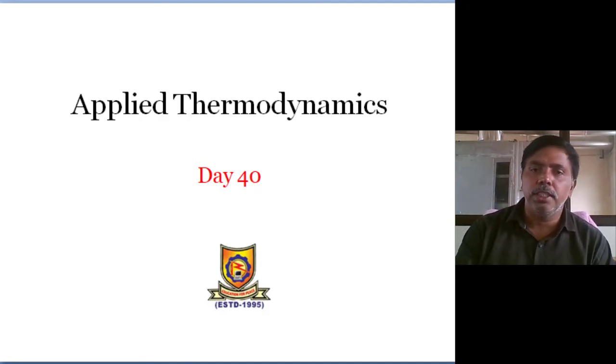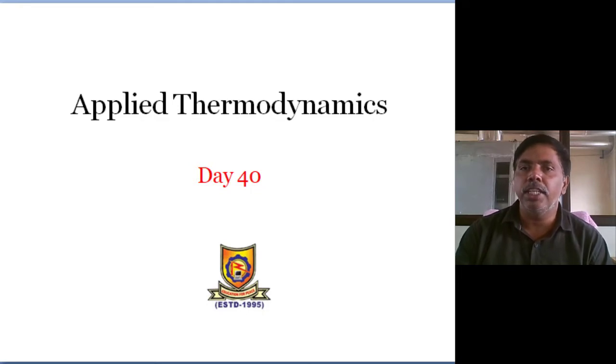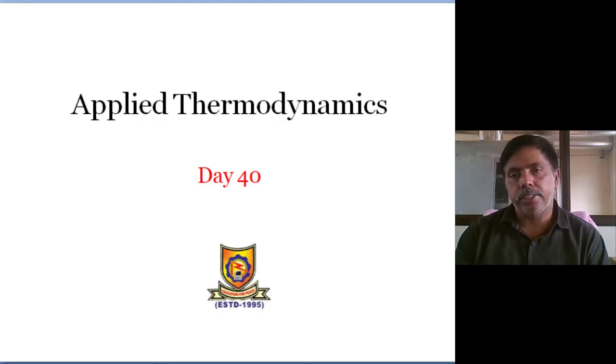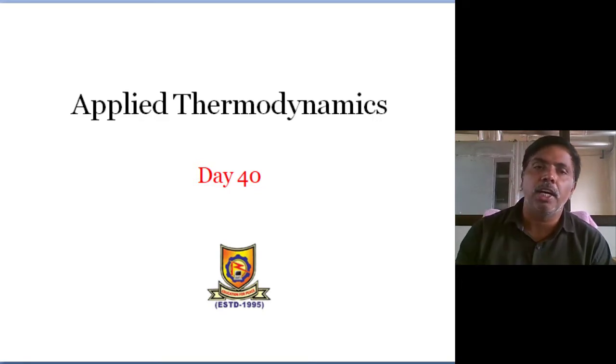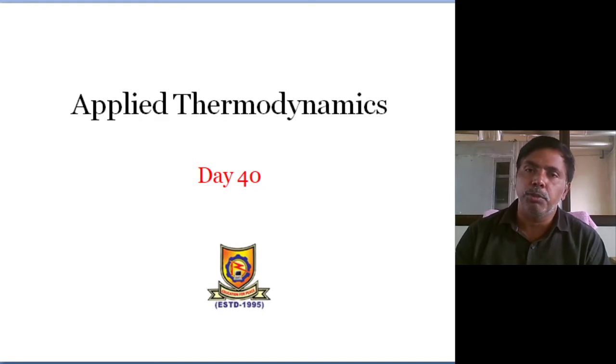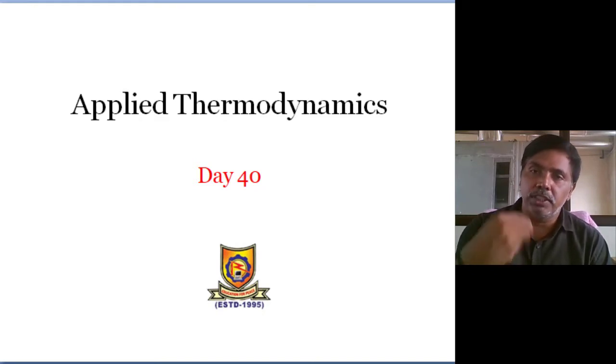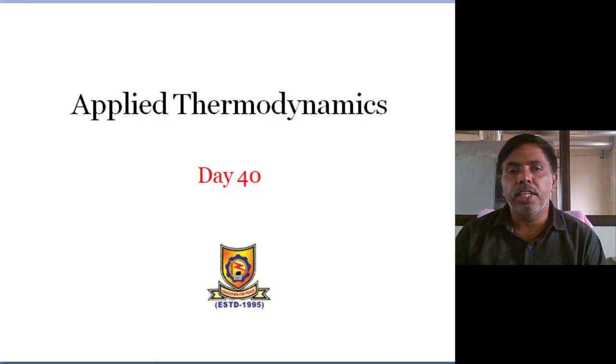That's why generally in HVAC, heating, ventilation and air conditioning systems, their high employment is there. We are simply measuring dry bulb and wet bulb. That's the simplest measure. With 100 rupees we can measure both. Based on the two temperatures, we extract all the remaining properties. What is the relative humidity? What is the moisture content? What is the enthalpy of the air? What is the specific volume of the air? Everything we can extract.